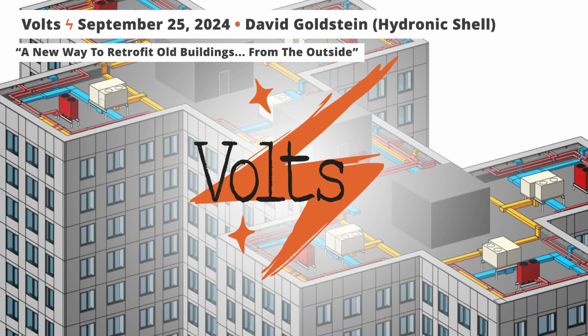So that's warm, dehumidified air basically circulating in that cavity, keeping it dry. I'd call it tempered air, probably around 60 degrees, though it depends on the season and how you want to operate the building. It'll probably be in the 60 to 70 degree range.